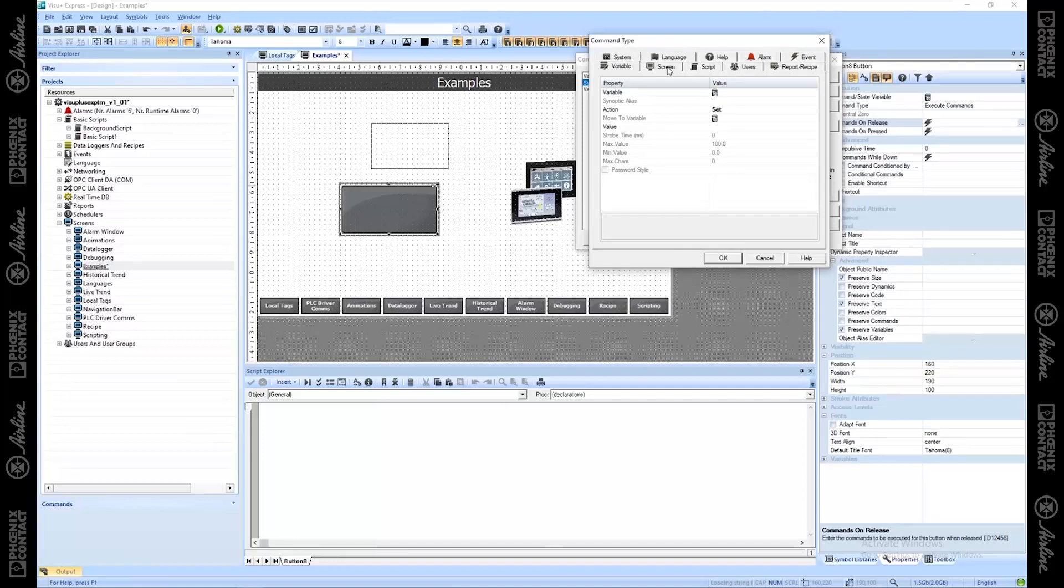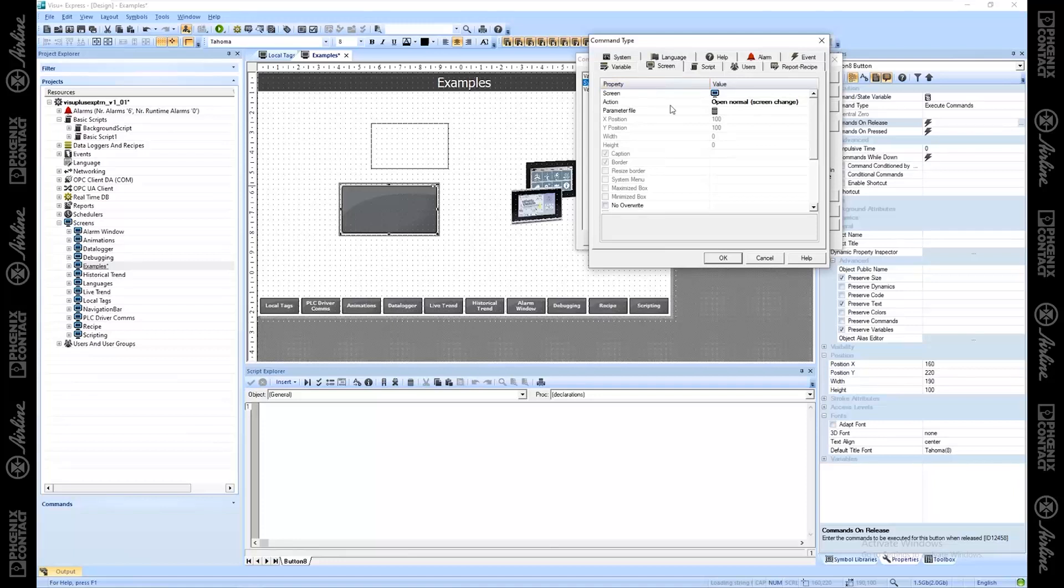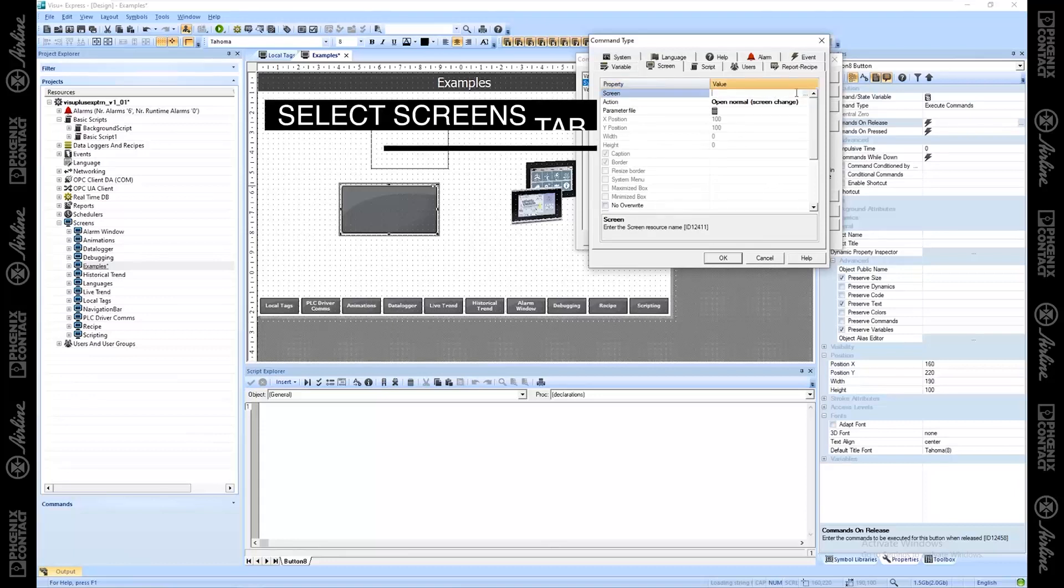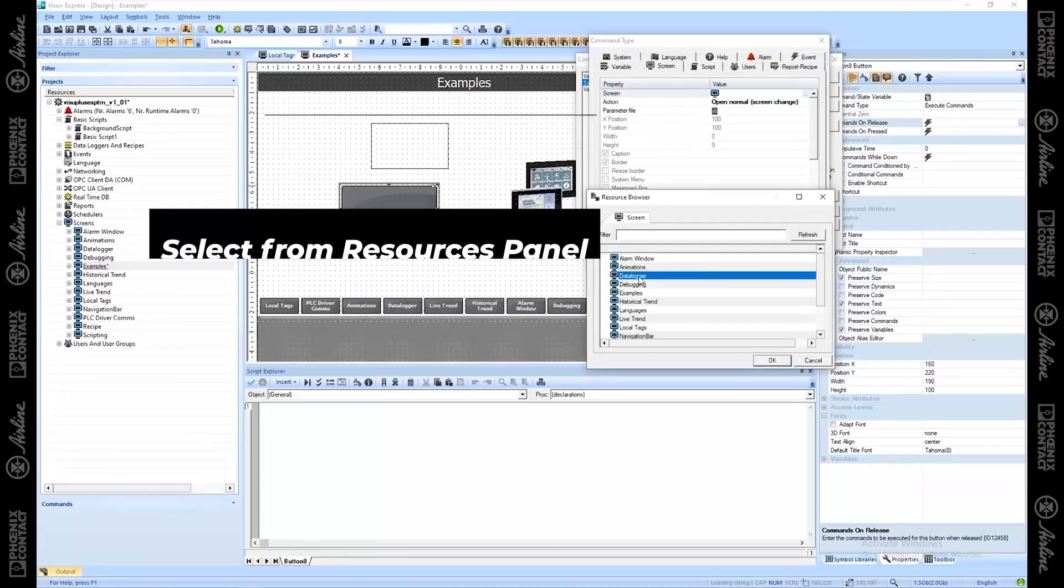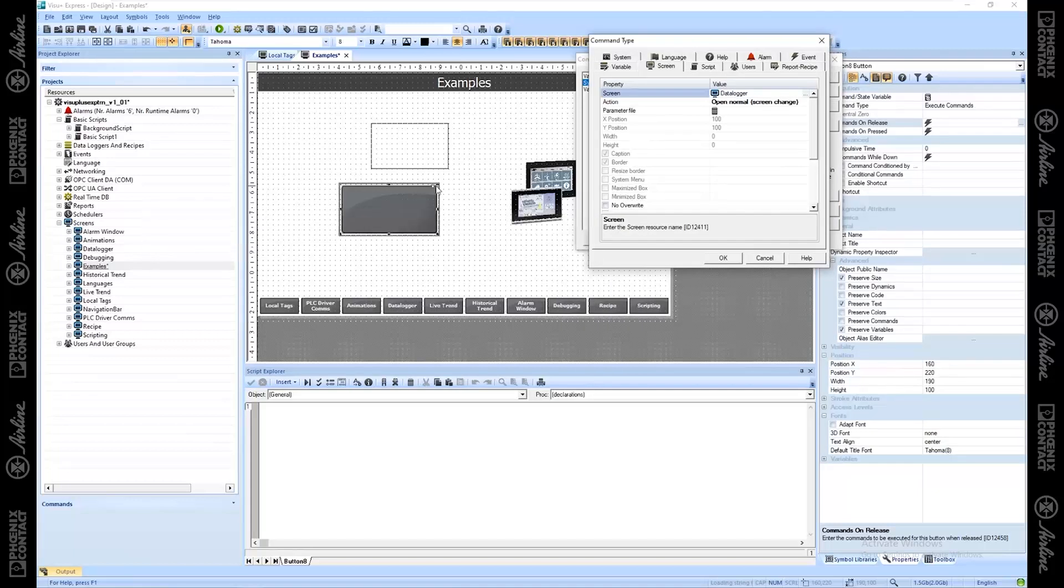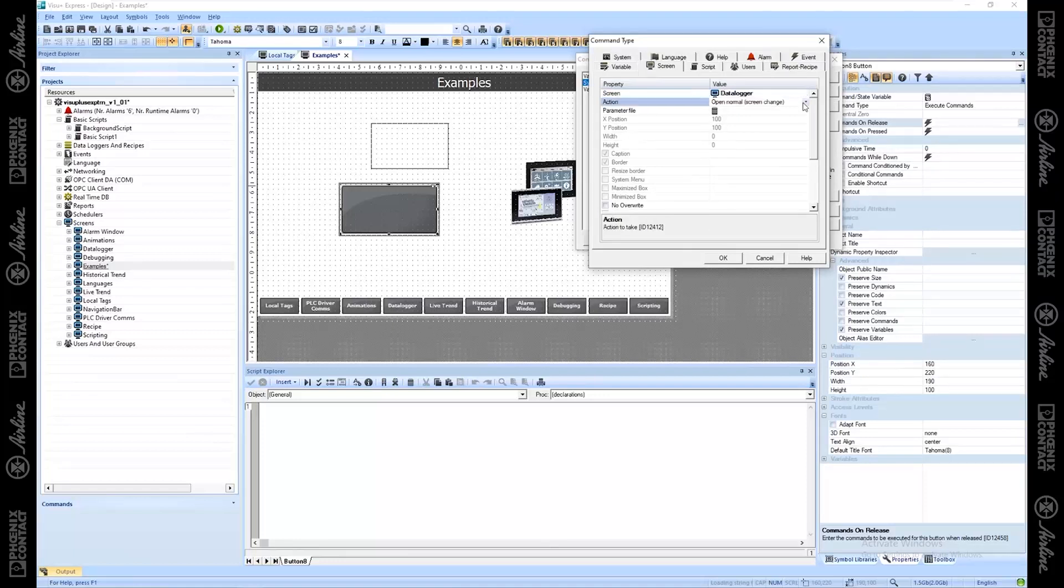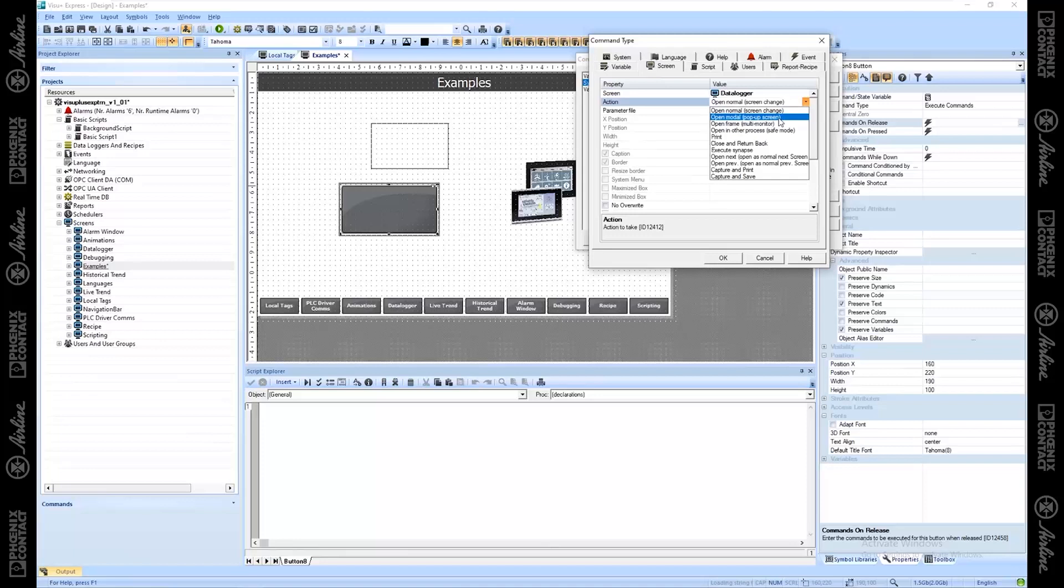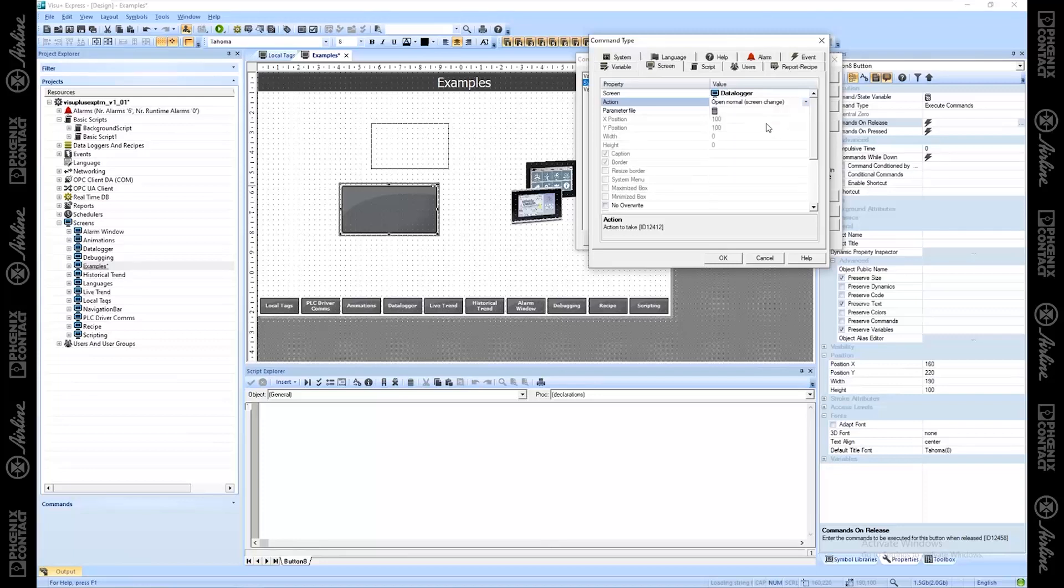We have variables, screens. This is going to be very common and useful. In fact, this is how your navigation bar works down here. If you want to open a screen, you go to the screens here, and you say, I want to open data logger when I press this button as well. The action right now is open normal. So that's just going to open a screen like a regular screen change. But you have a lot of options here as well. You can say, give me this as a pop-up window. If you have multiple monitors, if you're running on an IPC and you have multiple monitors, you can say, I want to put this on monitor one, on monitor two, on monitor three. And you can configure that there as well.